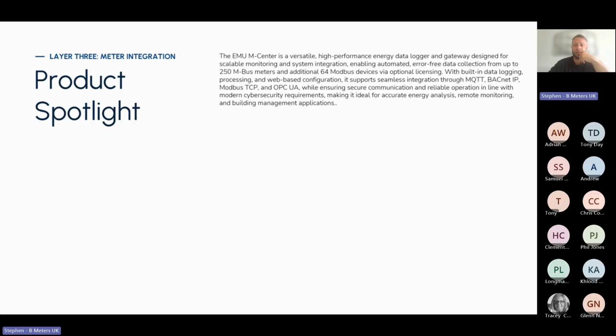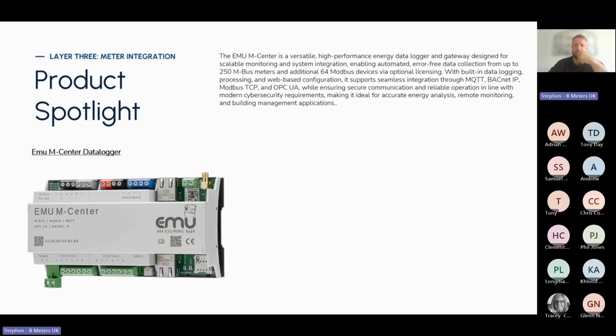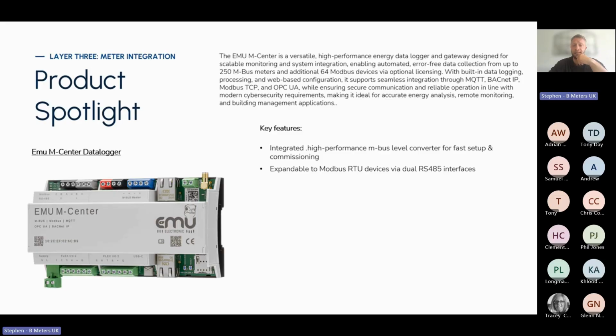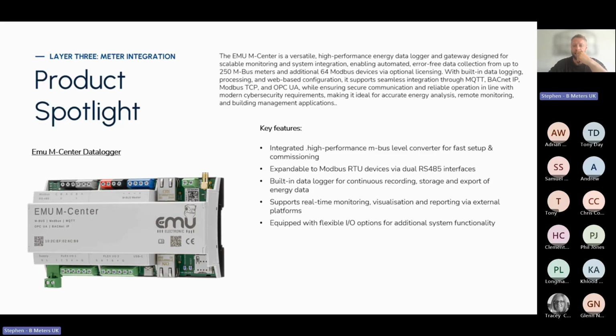share within the UK. So this is the EMU M-Center data logger. It's a versatile, high-performance energy data logger designed for scalable monitoring and system integration, enabling automated, error-free data collection for up to 250 M-Bus meters, and additionally 64 Modbus devices via optional licensing. The key features are an integrated high-performance M-Bus level converter for faster commissioning, expandable to Modbus RTU devices via dual RS485 interfaces, and a built-in data logger for continuous recording, storage, and export of energy data. It supports real-time monitoring, visualization, and reporting via external platforms, and is equipped with flexible I/O options for additional system functionality. Compatible with MQTT, BACnet IP, Modbus TCP, and OPC UA.